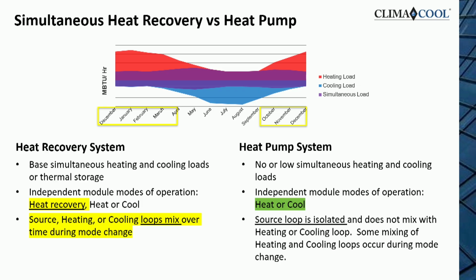And really when we talk about 6-pipe, we're talking primarily about heat recovery, right? Simultaneous. So what does that mean? You've got a base heating load and a base cooling load, or you're doing some kind of thermal storage. And sometimes the refrigerant circuit in those cases is actually very simple equipment. It's just a straight chiller that's connected to a load, and we're modulating on the water side. And that's, I think, really the beauty of the product: it's simple, it's flexible, and it's scalable, and it really opens up the ability to put simultaneous systems at lower load levels.